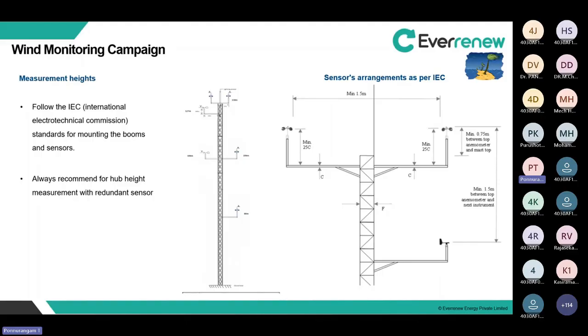And again, when you go down, there will be huge variation. Because when the blade rotates, it comes to the bottom position and also goes to the top. Between bottom and top there will be huge variation in wind speed, which creates fatigue on the turbine blades. To avoid that, we have to find an optimum hub height level. That's the reason sensors are fixed at different heights.